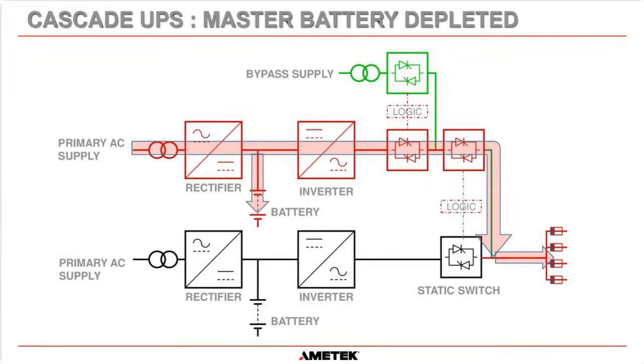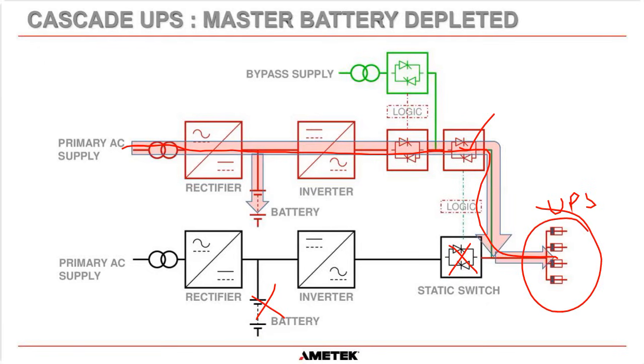And then if that battery depletes, once again, we turn this static switch on, we turn that static switch off. It's a make before break supply. But in this instance, now there's a UPS that is feeding the bypass for UPS-A. So we still have UPS backup and UPS protection to these loads here. It is still clean and regulated power going to the load circuits in this circumstance.